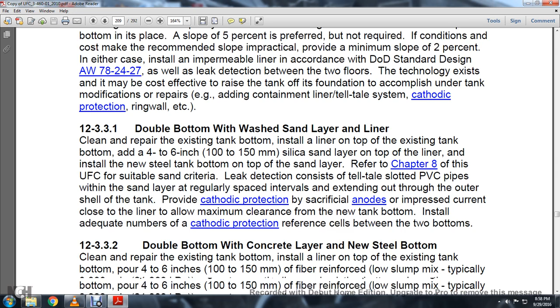12332 Double bottom concrete layer with a new steel bottom. Clean and repair the existing tank bottom and install a liner over the top of the existing tank bottom. Place 4 to 6 inches of fiber reinforced concrete, typically 3000 psi, over the liner of the existing bottom, shaped to provide adequate slope. Install the new steel tank bottom on top of the concrete.